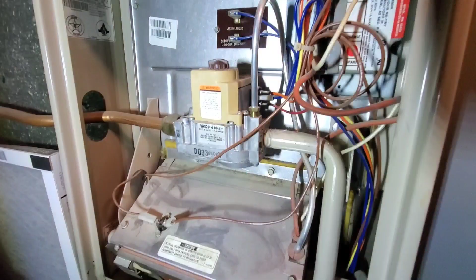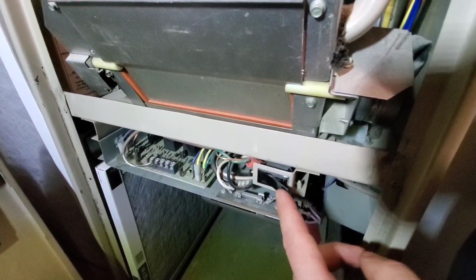All right, so for our furnace, we have our gas coming into our gas valve. The gas rail goes down into the burner assembly that is down here. So when there's a call for heat, this damper will open to allow air to come in. So if you guys don't actually want to shut the breaker off, if you don't know what it is or for whatever reason, because this is only 24 volts, this end switch here, when the cover's on, it'll depress the end switch. If you don't have the cover on and this end switch is not depressed, the furnace will never start. It's a safety feature. So if your furnace is not turning on, make sure that the cover, which is right here, has been installed to close the end switch here.